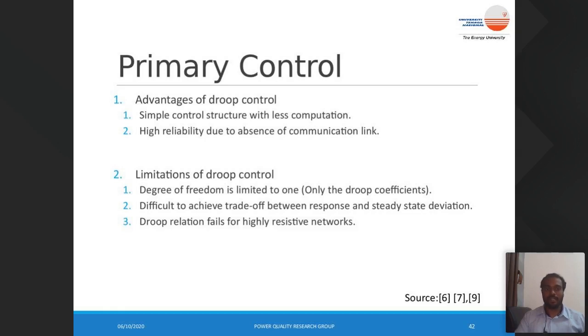And one more important thing is that these droop controls for inverters or converters are derived assuming high output inductance, which is predominantly not the case with microgrids, where the resistance dominates the inductance. So various modifications have been made to the droop techniques so that they also ensure accurate power sharing in a highly resistive network. And you can find those details in source number 9, which is by Professor Joseph Guerrero.